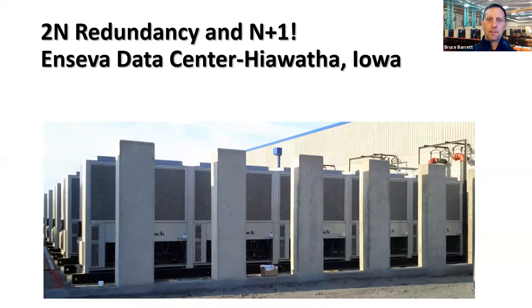We've got three banks of five modules each. Two of those modules happen to be free cools, making 50 degree water, which is warm from a comfort cooling standpoint. So the free cooling in Iowa gets a tremendous amount of run hours without beating up compressors at 10 degrees or less, for example.